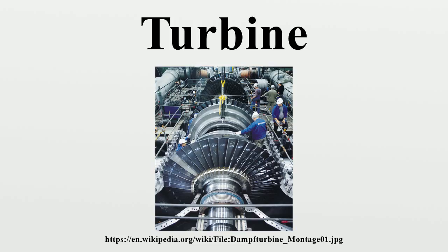turbine, with lacing wires. These wires pass through holes drilled in the blades at suitable distances from the blade root and are usually brazed to the blades at the point where they pass through. Lacing wires reduce blade flutter in the central part of the blades. The introduction of lacing wires substantially reduces the instances of blade failure in large or low-pressure turbines.